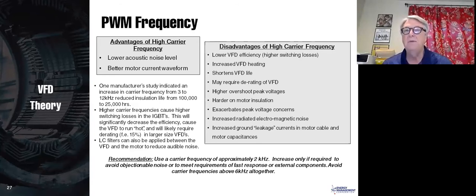The only time that I would go higher than that is if my motor was very, very noisy, in which case I would maybe go to 3 kilohertz, maybe even 4 kilohertz, see what it sounds like. We did a hospital at one point. I had 45 drives. The manufacturer sent the VFD at 8 kilohertz, and I went, this doesn't make any sense.